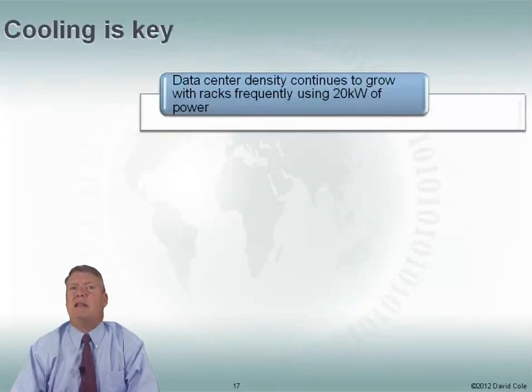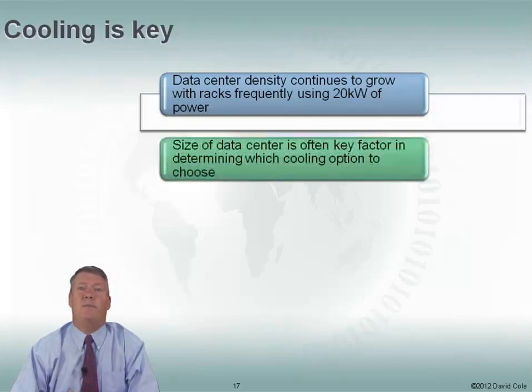Cooling is a key part of the data center. Data center density continues to grow. By density, I mean how much power we're using at a rack level. A typical data center was built for maybe 3 kilowatts of power in a rack. Now we've got racks using 5, 10, sometimes above 20 kilowatts of power. Cooling that becomes very, very difficult.